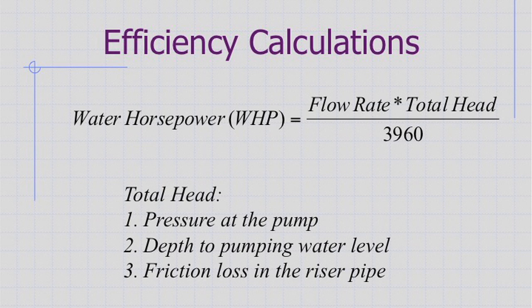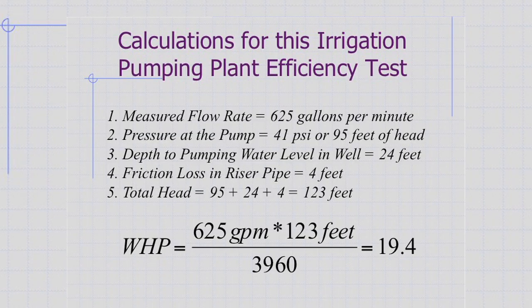The total head is the pressure at the pump, which we measure with a good pressure gauge, the depth to the pumping water level, and then an estimate of the friction loss in the riser pipe, which is usually a small value. Once we have that, we can calculate the water horsepower. Looking at the calculations for the test we just did, the measured flow rate was 625 gallons a minute. The pressure at the pump was 41 pounds per square inch, or 95 feet of head if you convert it to a head of water.